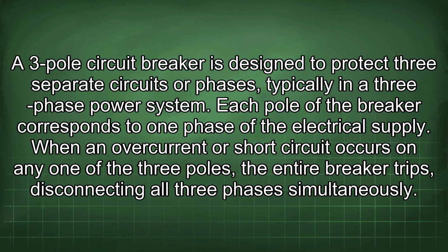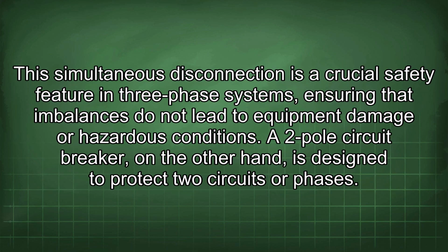A 3-pole circuit breaker is designed to protect 3 separate circuits or phases, typically in a 3-phase power system. Each pole of the breaker corresponds to one phase of the electrical supply. When an overcurrent or short circuit occurs on any one of the 3 poles, the entire breaker trips, disconnecting all 3 phases simultaneously. This simultaneous disconnection is a crucial safety feature in 3-phase systems, ensuring that imbalances do not lead to equipment damage or hazardous conditions.